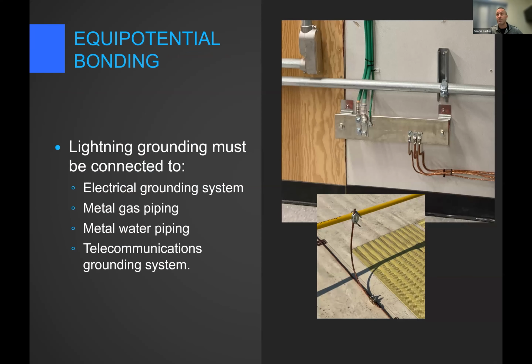Well, I'll get into it now. Equipotential bonding - yes, we have to be connected to all of those things. That's not just in the lightning protection codes, it's in the CSA, it's in the CE code too. So we have to be connected to the electrical grounding system.